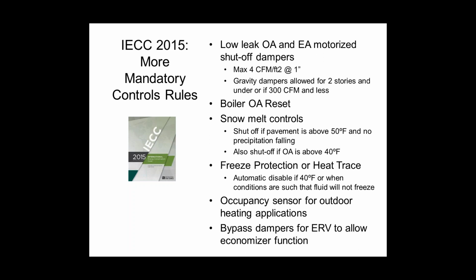And then if you're going to have an ERV, whether it's code required or whether you chose to do it, either way, from the control side, we have to have bypass dampers that will allow airflow to go around the ERV wheel or heat exchanger to give us an economizer type function. So if it's an economizer day and I'm trying to get free cooling from outside and I run my ERV, guess what? I'm warming up that air with the ERV, which I don't want to do. I want free cooling. So I have to shut off the ERV and open up bypass dampers to directly allow that airflow to come around that heat exchanger.